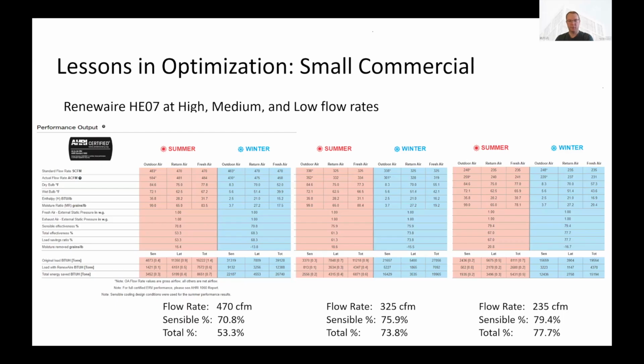And if we just reduce that down to 325 CFM, so again, less airflow, slower, more heat transfer, we see that sensible percent jump up to almost 76%. And reduce the flow further, we see that jump up to 79.4%.